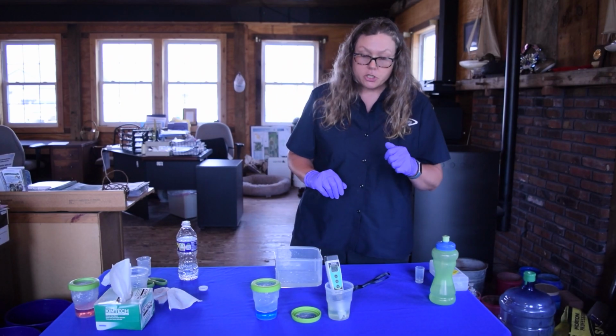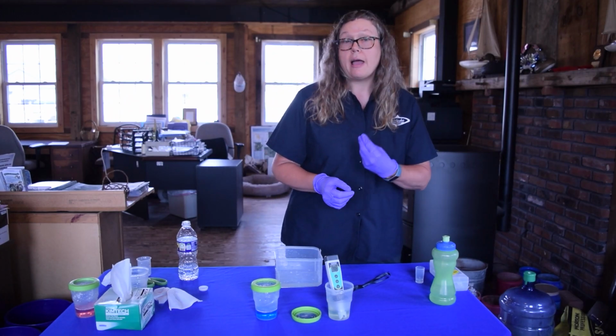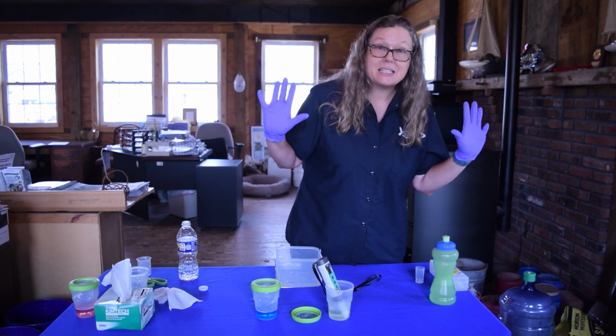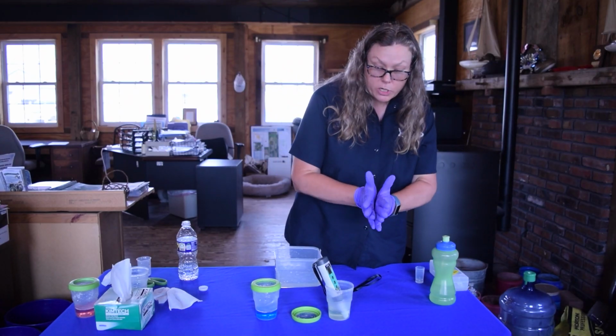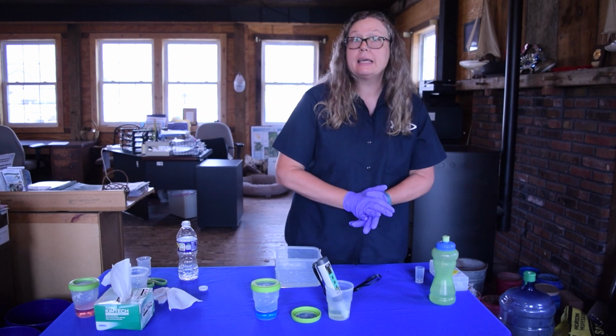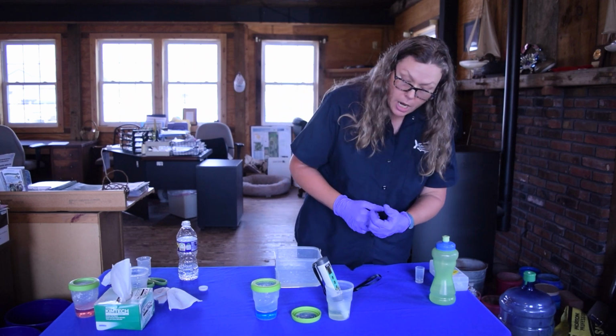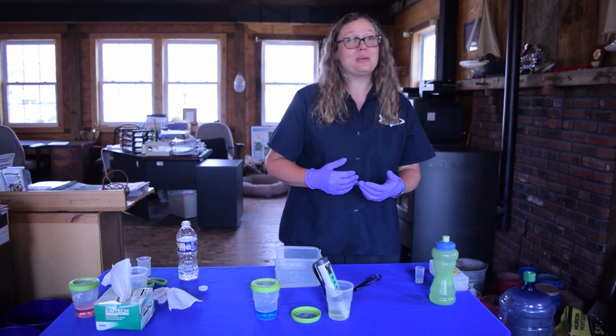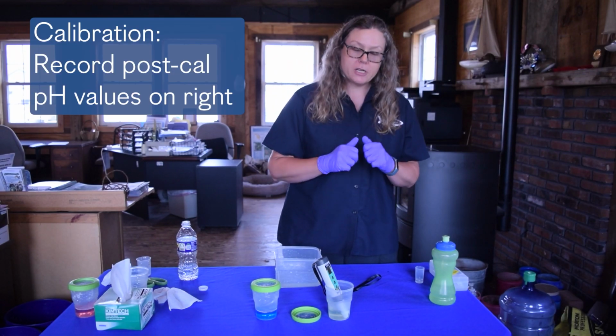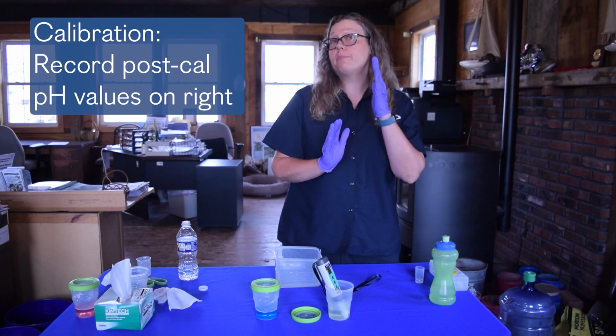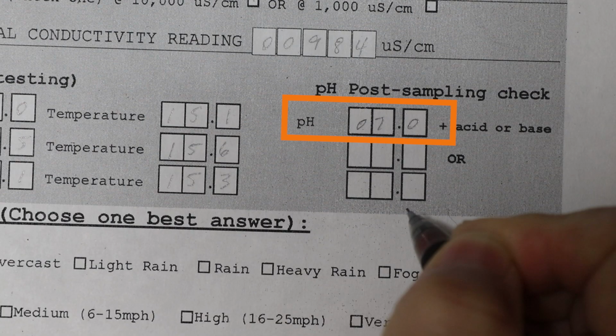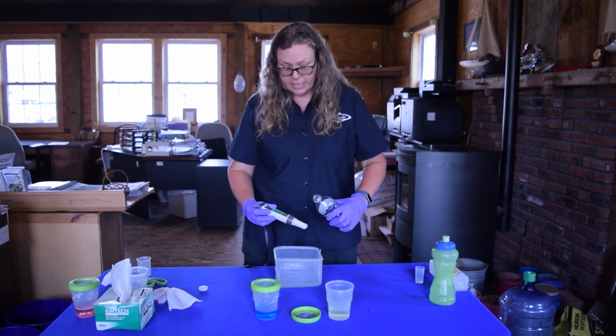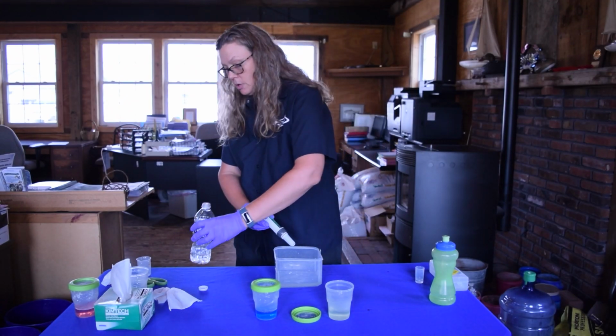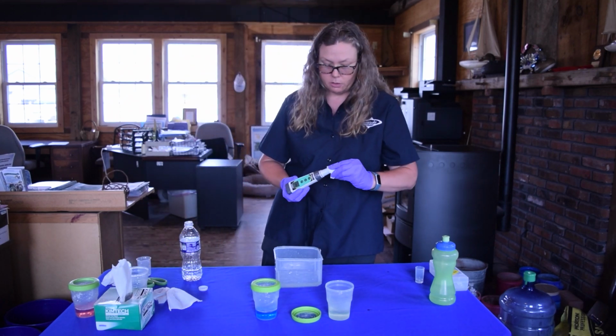So again, just as when we took a field measurement, we are not pressing anything once we turn the meter on. We are simply putting it in the solution to obtain a reading. And look at this. Our meter's very happy. It's saying 7.00. Perfect. So we only are going to record the pH value. Again, we're not going to record the temperature here. We only need the pH value, and we're going to record that on our site sample data sheet. After we have gotten the reading, we're going to do another rinse and wipe, which is our standard maneuver at this point.